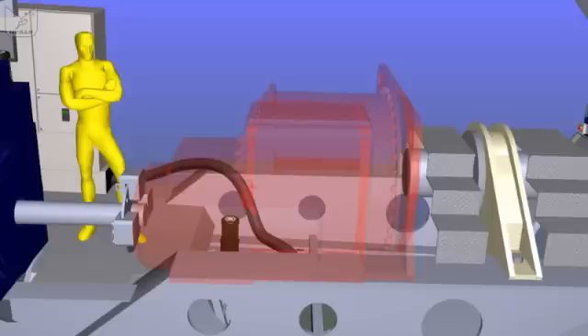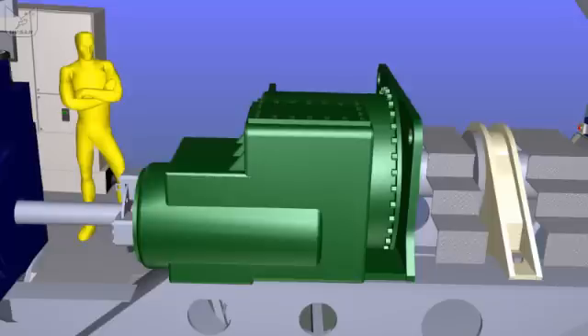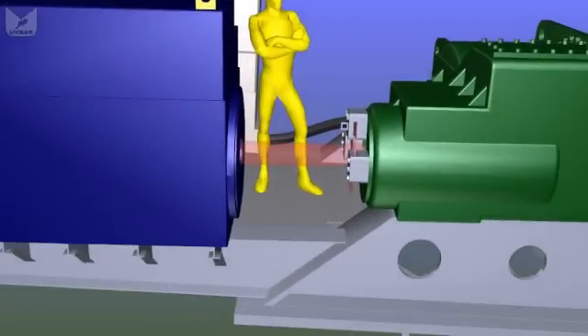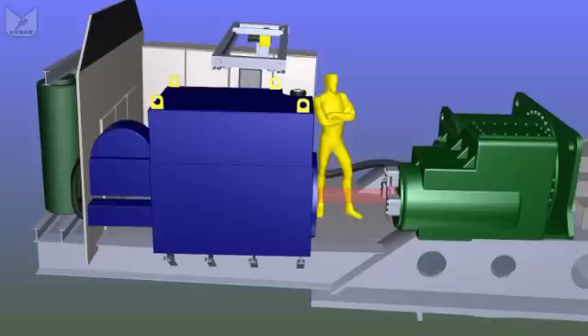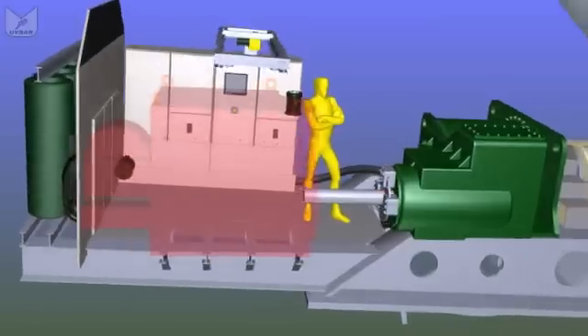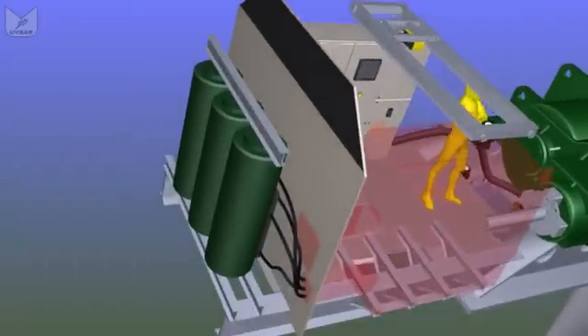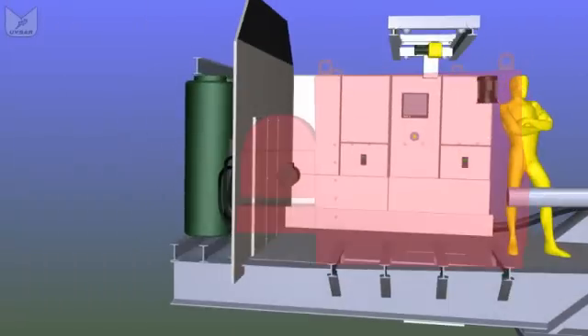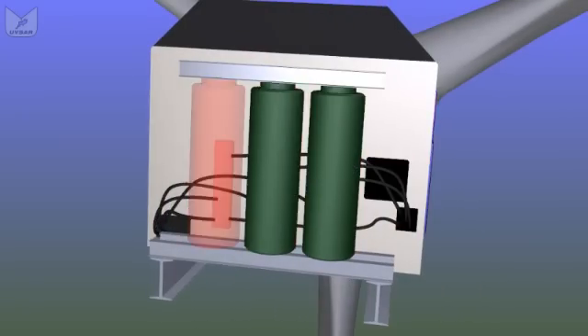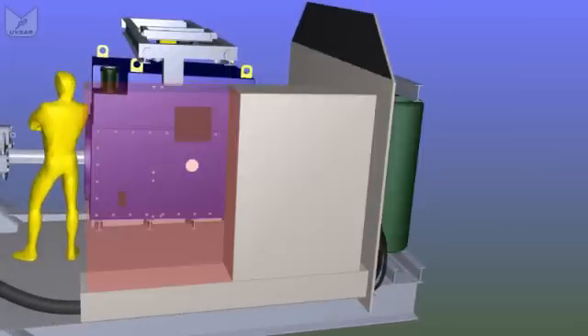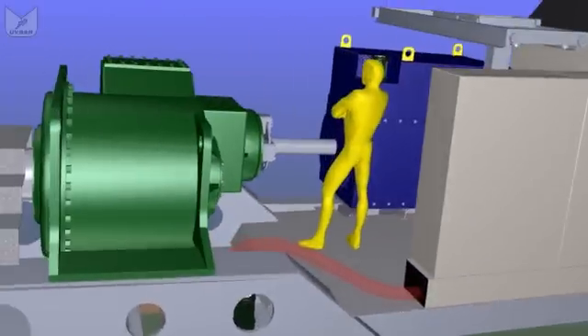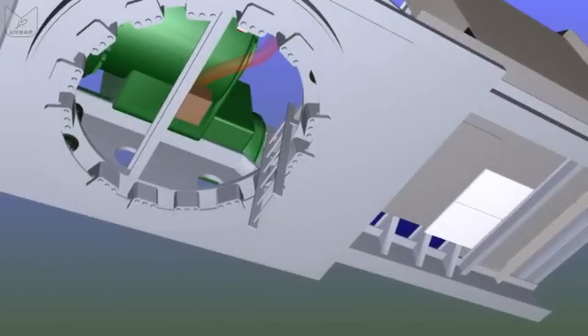So our main shaft drives our gearbox, which is mounted centrally because it's often the heaviest component. Out of the back comes a high-speed shaft, as before, that's where the braking system is. High-speed shaft then drives the generator, which is usually oil filled. The generator then supplies 690 volts, in this case into our transformer, which is sitting right next to it. That high-voltage signal then passes through the switchgear and the cabinet, down the dropper cable, straight down to the bottom of the tower, through those switches on platform two and off to the substation.